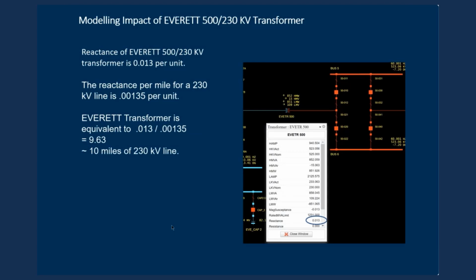Now we also have to account for the impact of transformers. At Everett, we have a 500 to 230 kV transformer, and its reactance is 0.013. In working with the Cascadia system, it's important to remember that the reactance per mile from a 230 kV line is 0.00135. So if we convert that transformer to the equivalent miles of 230 kV, we take the 0.013 divided by 0.00135, and that is close to 11 miles of 230 kV line.